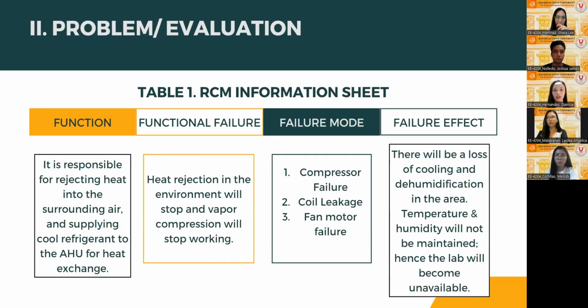Next is the condensing unit. The condensing unit is responsible for rejecting heat into the surrounding air and supplying cool refrigerant to the AHU for heat exchange. When heat rejection to the environment and the vapor compression cycle stop working, functional failure occurs. The causes of this functional failure include compressor failure, coil leakage, and fan motor failure. Less heat can be transferred from the refrigerant to the ambient air if the mentioned failures in the condensing unit occur. Thus, there will be a loss of cooling and dehumidification in the area. Temperature and humidity will not be maintained, hence the lab will become unavailable.